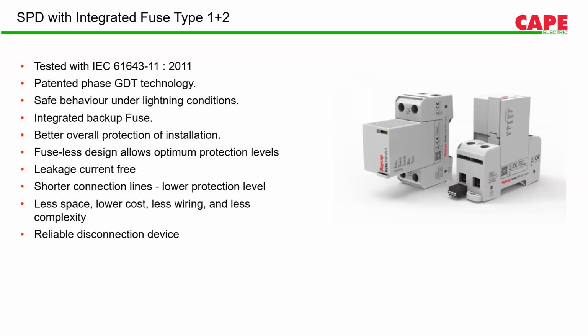It's again a reliable disconnection device. You don't have to really rely on a second device. The SPD has an inbuilt fuse, so the coordination is better. Impulse current up to 25 kiloampere, and most importantly, the short circuit current it can withstand is up to 100 kiloamperes. Now actually the short circuit current is one of the important parameters while choosing an SPD. Normally once we choose an SPD, the first thing we say is we need a 50 kiloampere surge protection device.